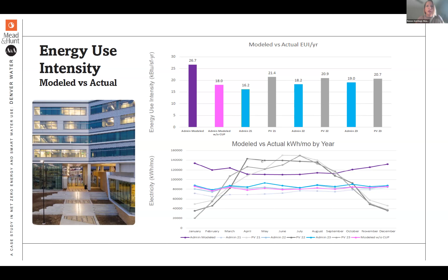So what was in this central utility plant? It's pretty sophisticated. Denver Water happens to have a huge water conduit running underground, so instead of ground source heat pumps, which are more expensive, we used heat exchange from the water conduit, plus thermal energy storage tanks for good heat exchange. When those aren't enough, we use air source heat pumps, and when those aren't enough, depending on the season, we use chillers or the backup electric boiler, for a combined COP plant efficiency for heating and cooling of about 6, which is really good. For example, electric boiler COP is about 1.